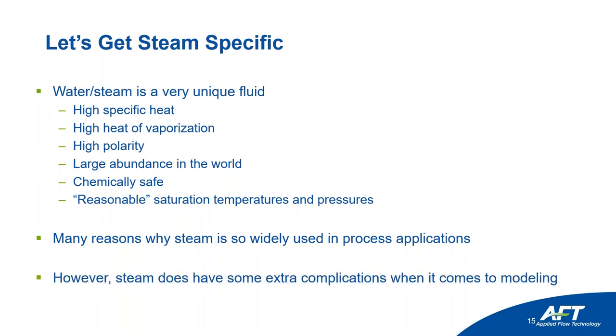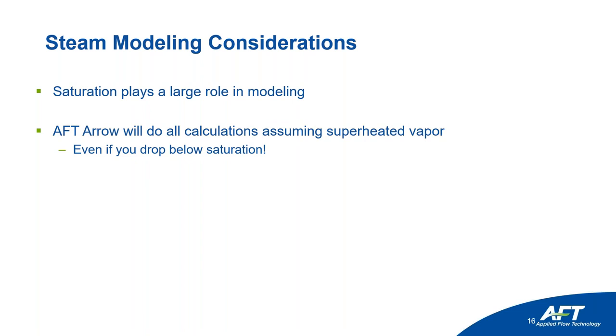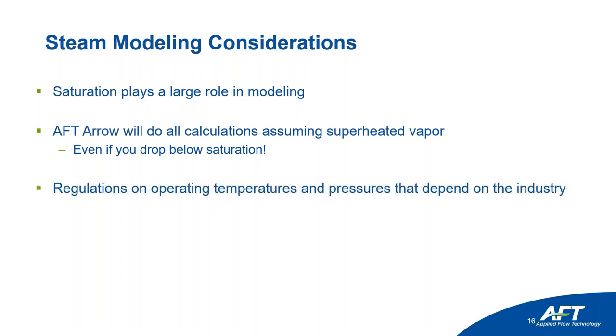However, steam has some extra complications when it comes to modeling. We have to pay attention to saturation — because those saturation conditions are reasonably approachable, we have to worry about steam condensing out in our piping systems. AFT Arrow will do all calculations assuming it's a superheated vapor — even if you drop below saturation conditions, it will still solve as if it were a gas, extrapolating data from a gaseous state. AFT Arrow will warn you that saturation is occurring depending on the database you use. You don't have to worry about this with air or oxygen, not usually unless you're in cryogenics.